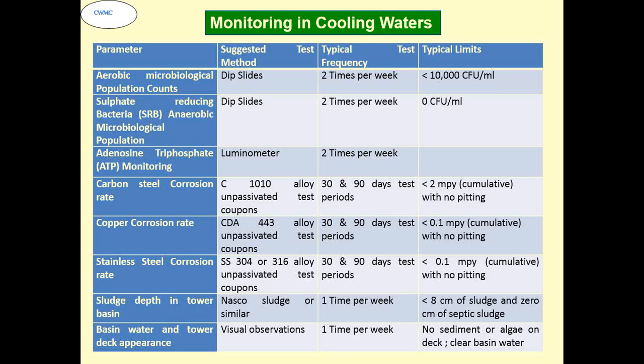Carbon steel corrosion using a C1010 alloy coupon, copper corrosion rate with CDA443 alloy, stainless steel SS304 or 316, sludge and depth in the tower basin, NASCO sludge or similar, basin water and this thing. But when we are using corrosion coupons, it is 30 to 90 days. The only thing we have to see is that it will give a cumulative corrosion rate. It will not tell you instantaneously what has happened. So for that you go for online monitoring.